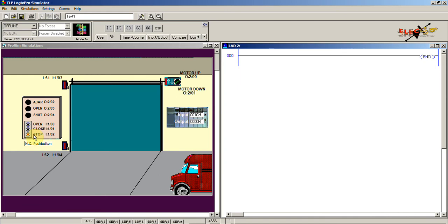One thing to keep in mind is that when we press the open push button, the door has to open, but once the door is opening, if you press the close push button, the door should not close until it reaches one of the limit switches. For that we are going to include an interlocking system, where once the door is opened, the door will be completely opened, or else if you press the stop push button, the door will be stopped there itself. Or if you press the other push button like close, the door should be closed, or if you press the open push button, the door should be opened.